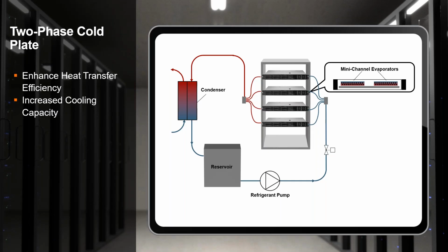So we're enhancing our heat transfer efficiency and increasing our cooling capacity. The reality is we can pull more heat out this way than with just single phase heat exchange. Another nice part is we get a much more uniform temperature distribution with two-phase systems. When I'm changing phase, I'm not really changing temperature, so the fluid stays the same temperature as it moves across the cold plate, pulling heat out much more uniformly. That's an interesting advantage of evaporative cooling processes like two-phase liquid cold plate.